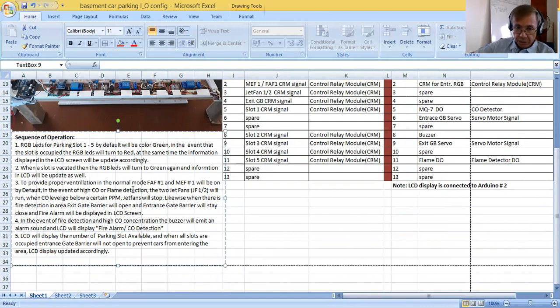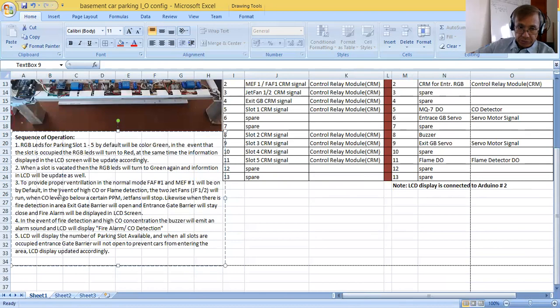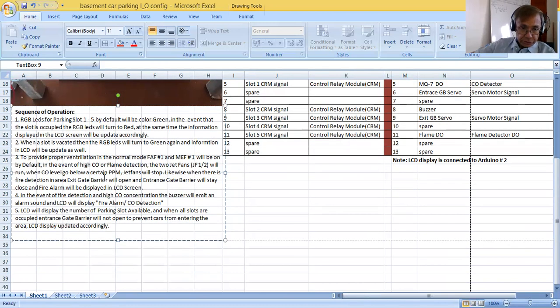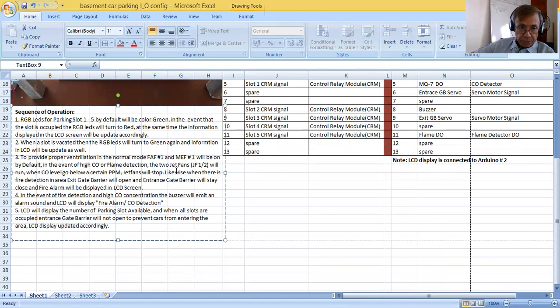Two, when the slot is vacated, then the RGB LEDs will turn to green again and then information LCD will be updated as well. Three, to provide proper ventilation in the normal mode, FAF number one and MEF number one, so FAF is Fresh Air Fan, then Main Extraction Fan, will be on by default.